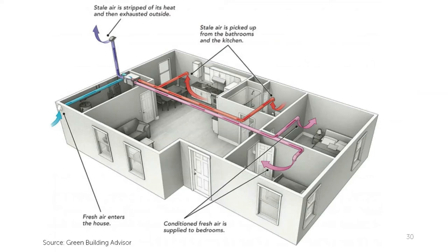In contrast, balance systems provide fresh air exactly where we need it and remove stale air from where we don't want it. Balance systems used in Vermont tend to be heat recovery ventilators or energy recovery ventilators. The exhaust air for these systems may be pulled from bathrooms and kitchens or another generalized location in the home, and the supply air may go to bedrooms and living rooms or another generalized location in the home. Where air is exhausted from and where it is supplied to makes a big difference for indoor air quality.